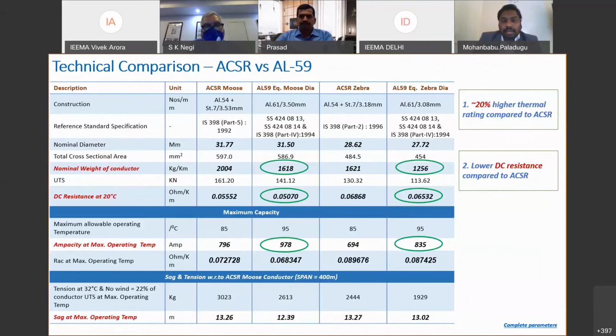The second part of the benefit is the weight of this conductor. If you see the weight of the conductor, it's around the nominal weight of ACSR Moose and AL59 Moose, or ACSR Zebra and AL59 Zebra, the weight is almost lesser than the ACSR conductors. So this helps in your tower optimization. So tower weights and tower optimization will be improved, so your overall project cost can be reduced. If you take any long distance lines, the overall project cost comes down.